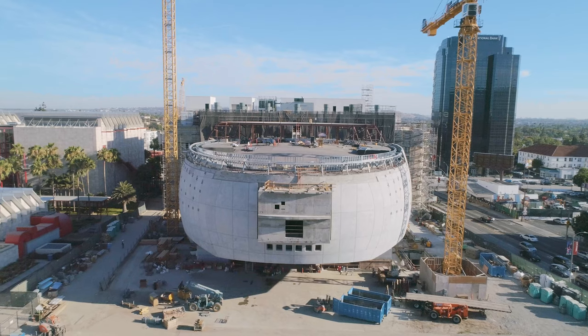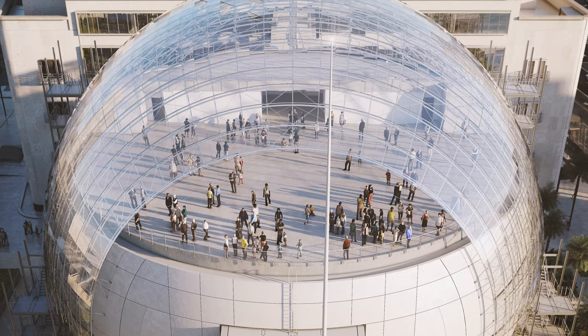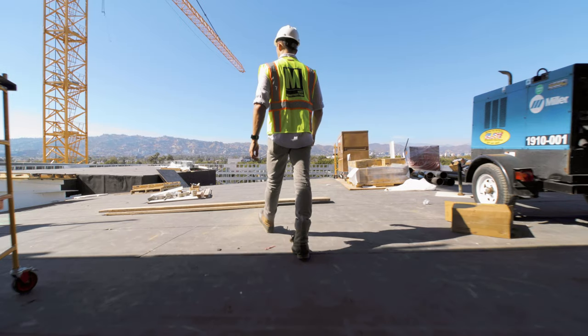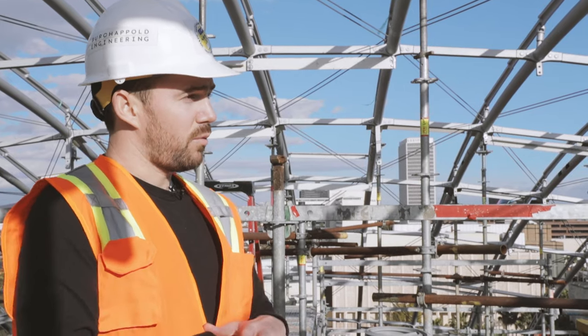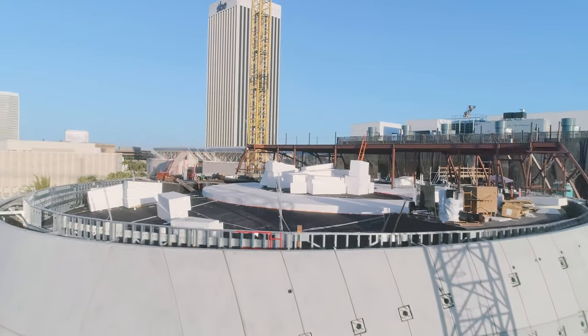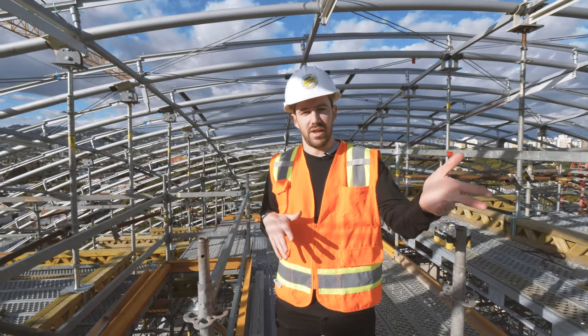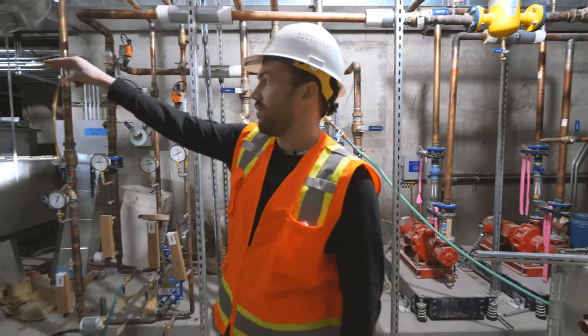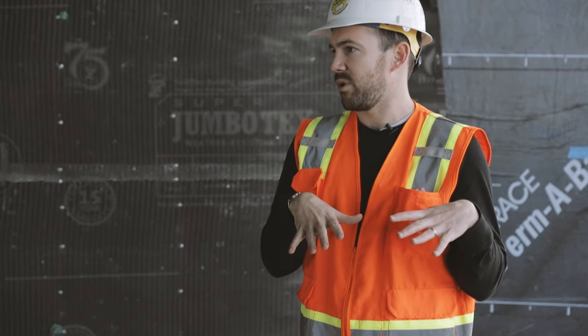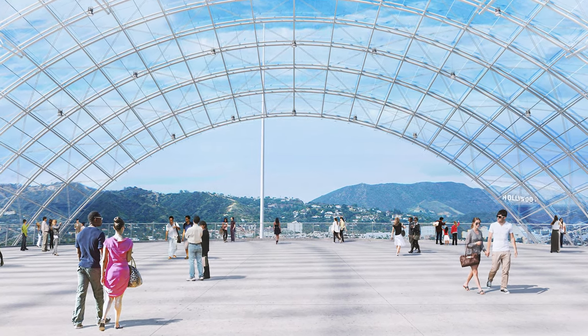This is the Dolby Deck — it's a large outdoor terrace covered with a glass dome. The entire terrace is exposed to the elements, so the dilemma as an engineer who wants to be sustainable is how do you condition an outdoor space without wasting energy. The terrace below is one large radiant floor slab which can be used for heating or cooling. We're capturing the rejected heat from the heat recovery chiller in the other building and using that in the radiant floor. So for a nighttime or evening event where people outside want to keep warm, we're pushing that heat into the radiant floor slab and providing some level of conditioning.